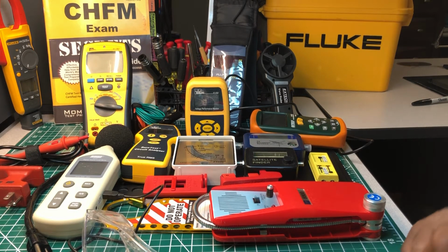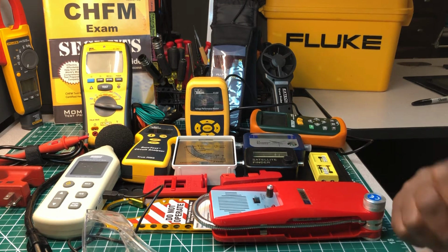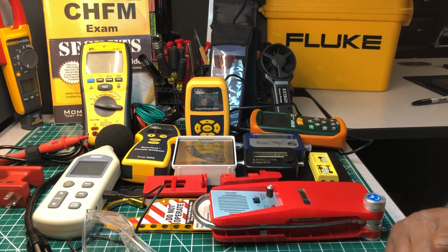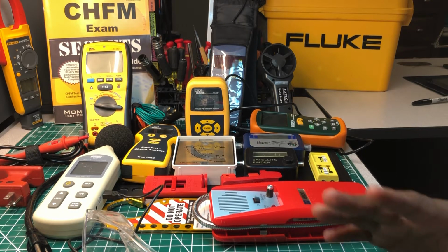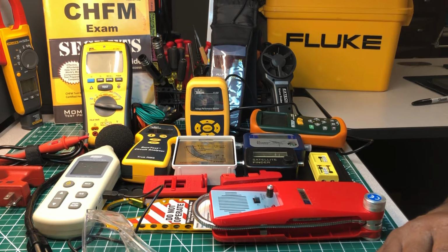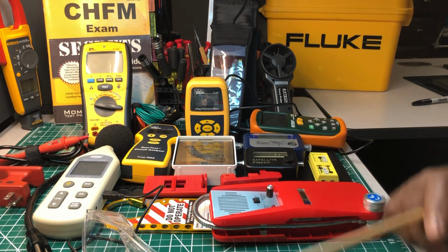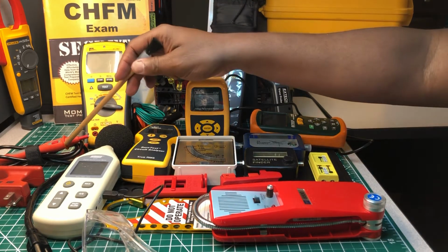Okay, next to it right here is my insulation tester. Working in that environment, a motor's going to go bad, and hospital is fast, man. You can't let nothing sit down, and you got to make sure everything is working up to its peak. So you got to do PMs on just about anything, even though it looks like it's running right. Every now and then you have to shut that off, and you have to test stuff and keep records of everything. So I used to test certain pumps. I turn them off, and I check the insulation on them. And I keep a record of all of that stuff. So this is the meter that I was using for that.